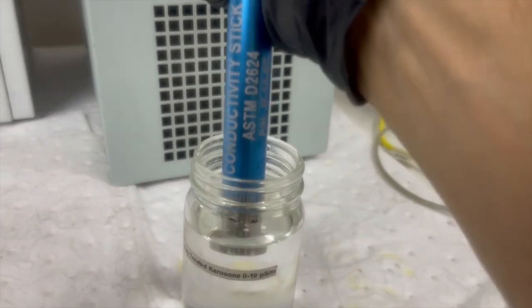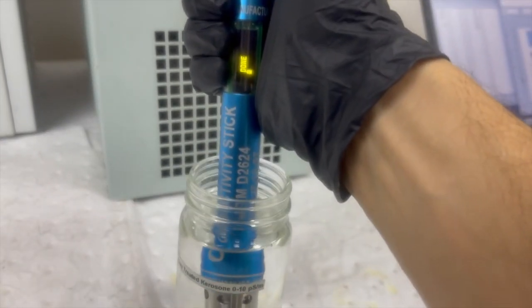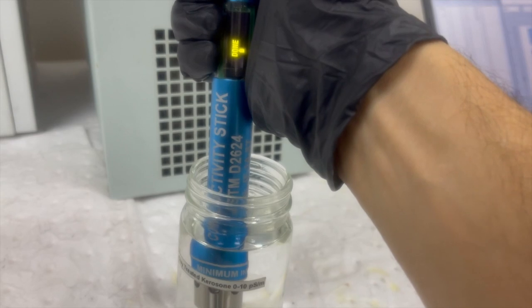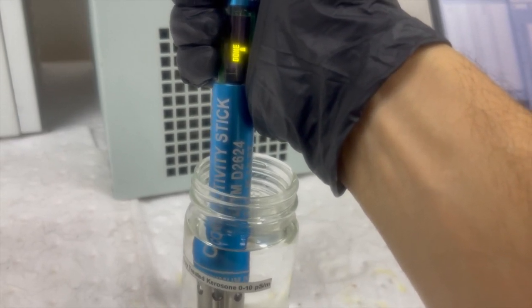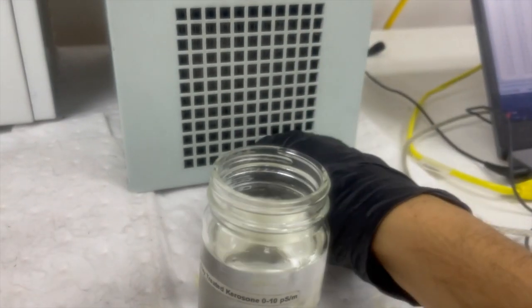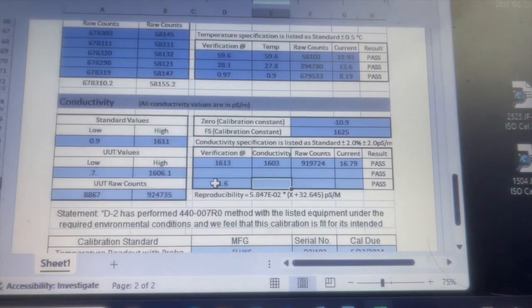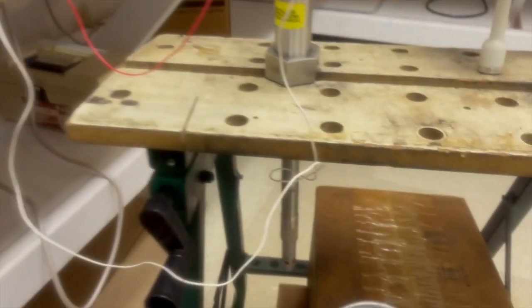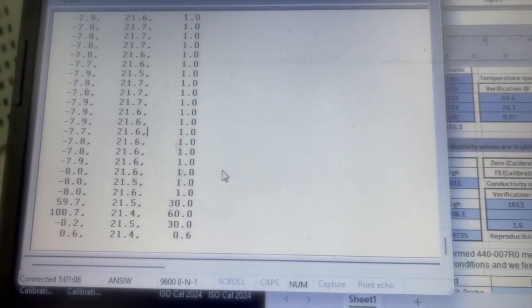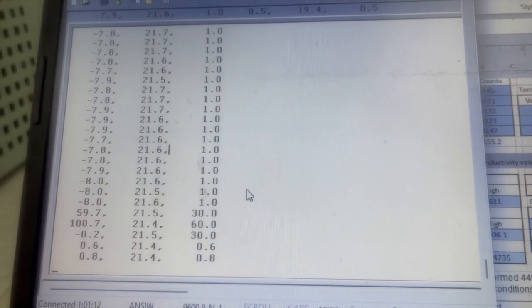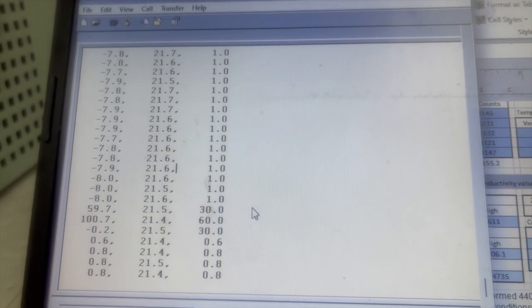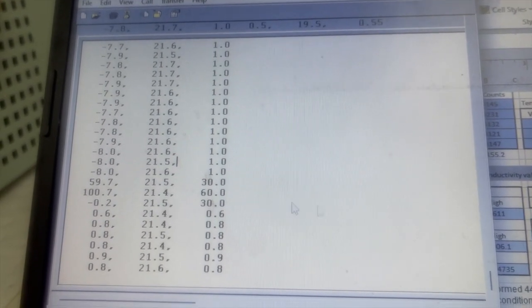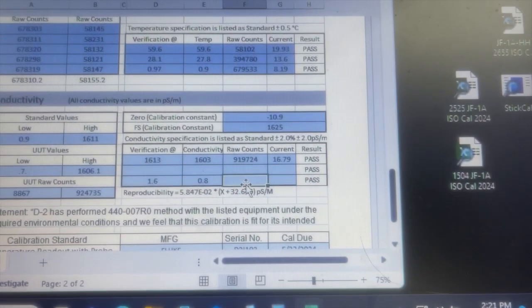Now we're going to verify the zero fluid. Now that we've calibrated the instrument, we're going to go ahead and get our zero fluid reference number. Say 1.6. So we plug that into our data sheet, 1.6. And then we're going to run the fuel against the inlet. Put the fuel on the sensor tip, and go over here and we get our reading off the sensor. We have to wait 7 counts. Okay, so our reading is 0.8, which is a pass.